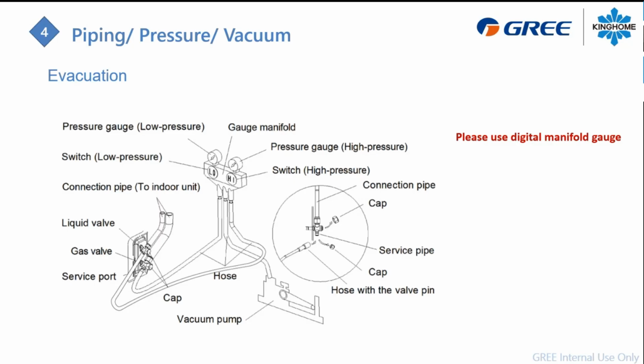Another tip and trick you can do is just crack the valve a little bit and close it already. Just make sure you apply some pressure into your pipe, and then you remove your gauges at this time if you don't want to lose too much refrigerant. If you have done with it, you can remove your gauges already at this point, or if you want to make your test and everything, you can leave them there. But the thing is, you can open the liquid line from the outdoor unit first and then make it cycle. Just be sure you open all 4 valves at the end.